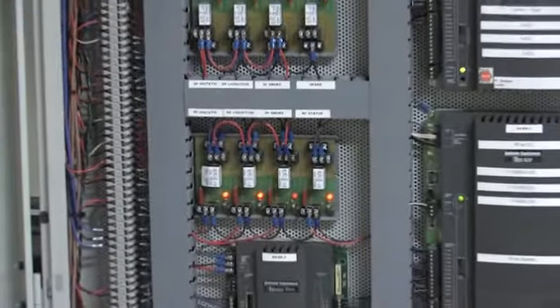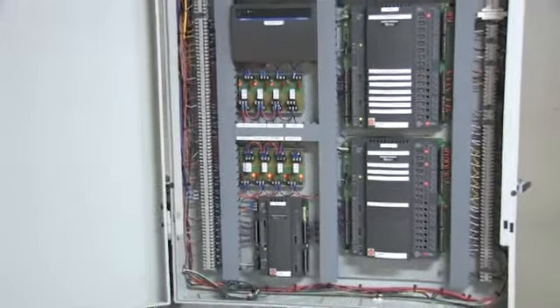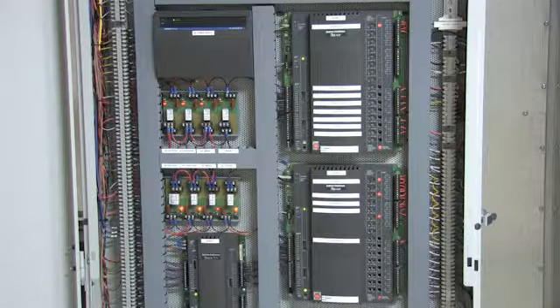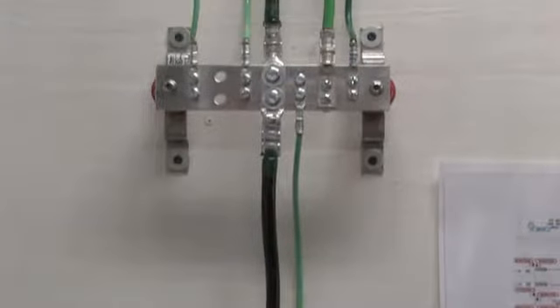As more facility and IT managers are taking building automation systems and bringing them onto IP protocol, it introduces new challenges. You are now having many of the control devices in an industrial environment. So it's very important that where you have a central plant, an industrial environment, that you have the proper enclosures, the proper bonding and grounding systems, and patching to ensure a seamless connection of those BAS devices over IP protocol. So at Panduit, we offer many different types of enclosures that have the bonding and grounding as well as the patching already integrated into the enclosures.